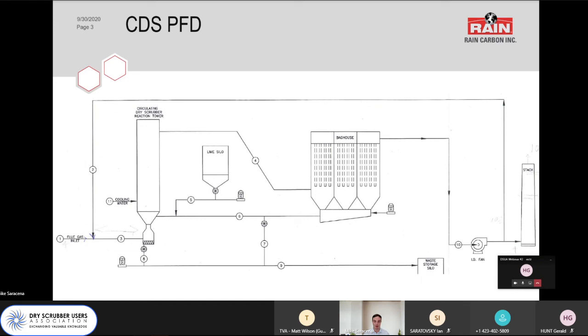It's difficult. It would be hard to have an accurate understanding of how much lime you're using at any higher resolution than about a week. That's also bad because there are times where we see what we think is high lime use for a few days and then it lines out. We don't really ever know. But I would definitely recommend, if you can, installing loss-in-weight feeders or even load cells on the silo, something to measure the mass of lime that you're using.